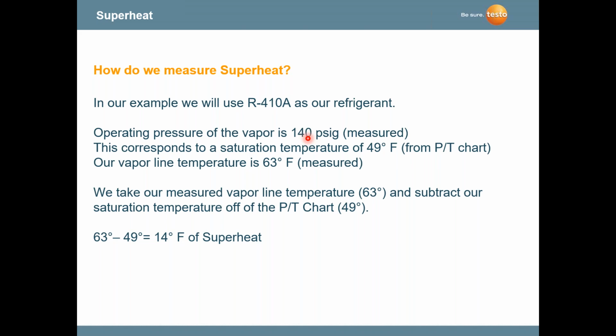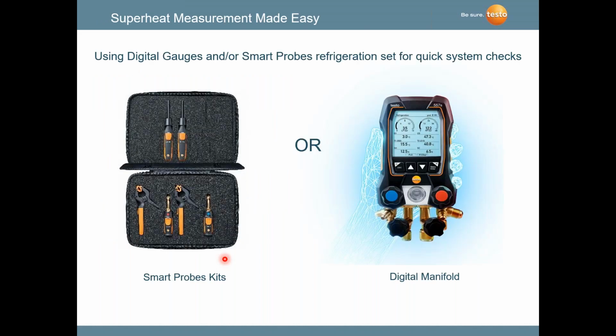We start at 0 on our gauge. So if we have 410A and we have 140 PSIG on our vapor side, or low pressure side, then we have to use a PT chart or a corresponding gauge temperature to get the saturation temperature of 49 degrees. We still have to measure our line temperature. We get 63 degrees. We just do a little bit of math and we get the superheat calculation.